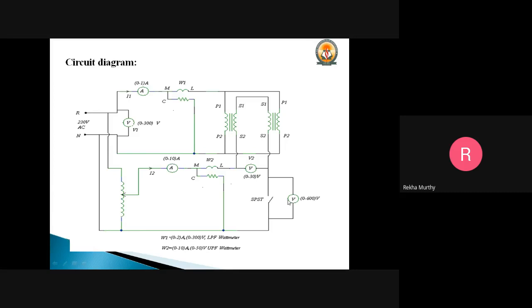Okay. Once the voltmeter reads 0, the SPST switch is closed. Now, by operating the auto transformer, the voltage is applied. Now we are going to switch on this. We are going to close the SPST switch, then vary the auto transformer such that the voltage applied is increased gradually till the windings carry the rated current. What is the rated current? 8.7 amperes for the 2 kVA transformer, as we discussed in the previous session. The readings of all the meters will be noted and tabulated. Then we have to bring the auto transformer back to the 0 voltage position, open the SPST switch, and then switch off the supply.